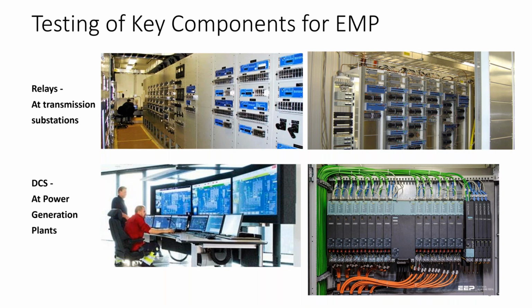The two components that we're going to be talking about are the relays, which are at transmission substations, and distributed control systems. So there's kind of the front end and the back end of each of those. They perform similar functions as command, control, and protection functions, and so their behavior is actually pretty similar. And when we do the tests, we're using the MIL standard 188-125 test.